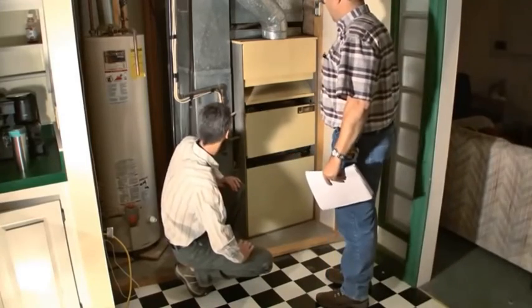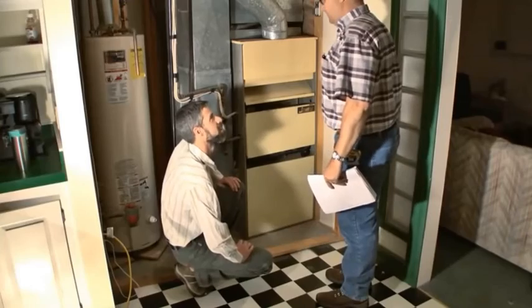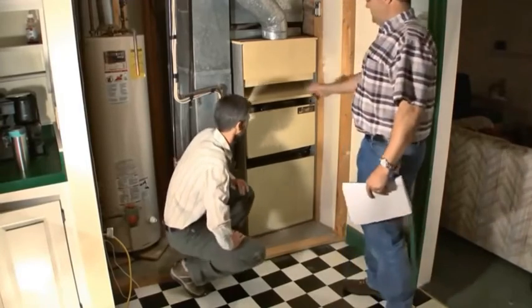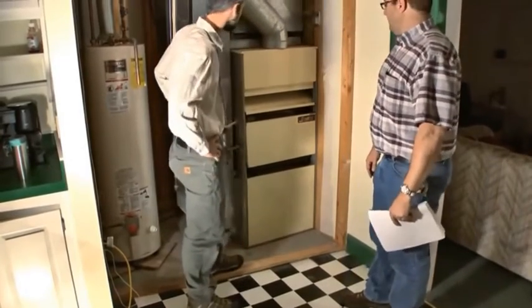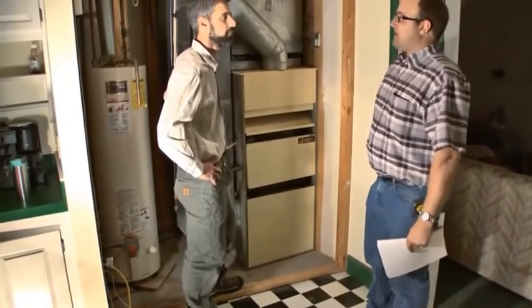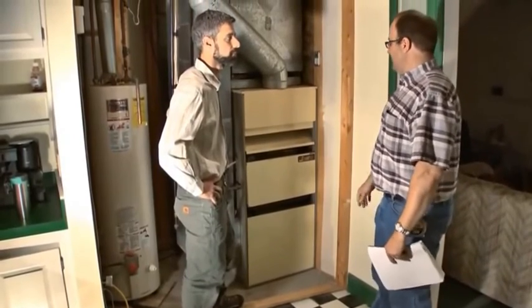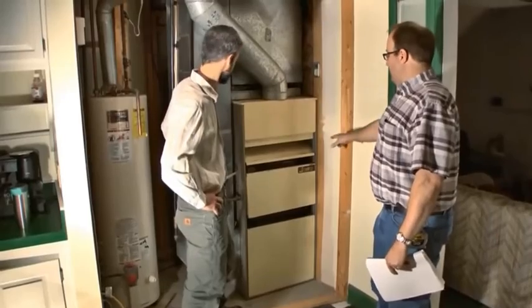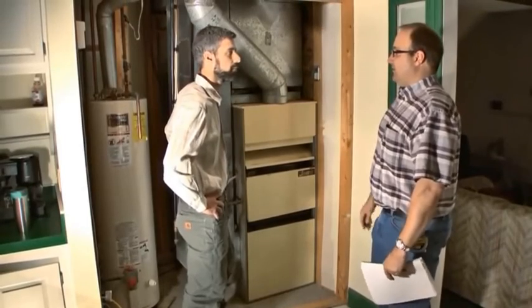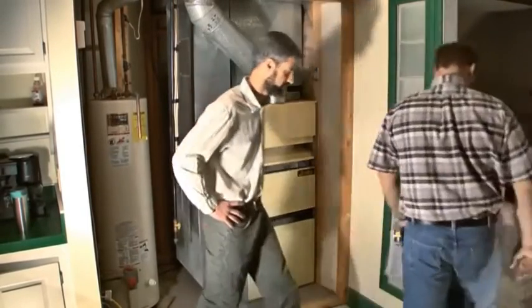So we got it running. You probably need to check how much gas it's using, huh? Yep, this is a natural gas system, so right now would be a really good time to go out to the gas meter, and we'll clock the gas meter and confirm the right amount of fuel is being supplied to this furnace. All right, let's go check it out. Yeah.